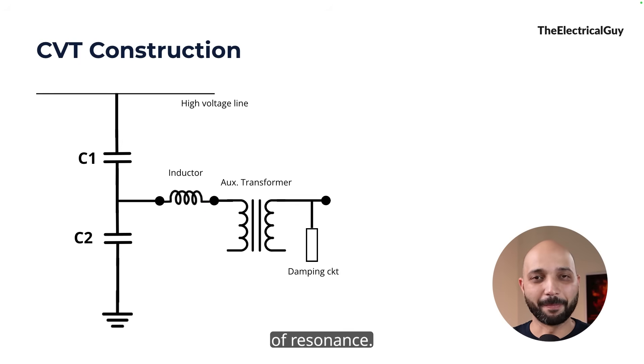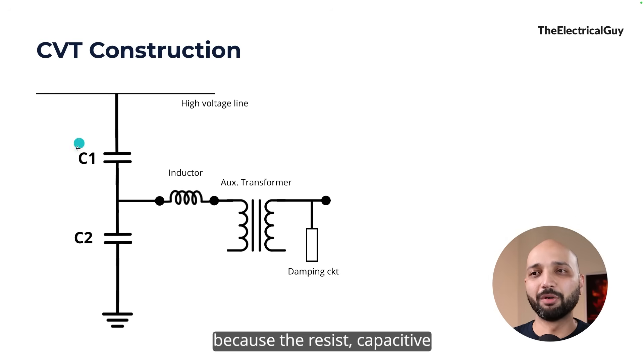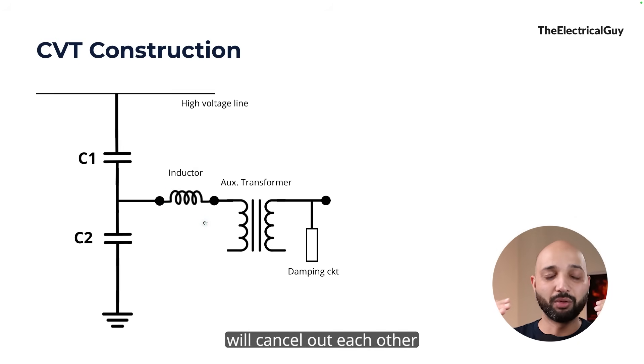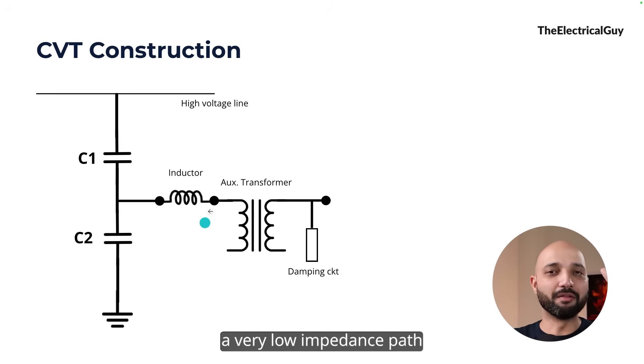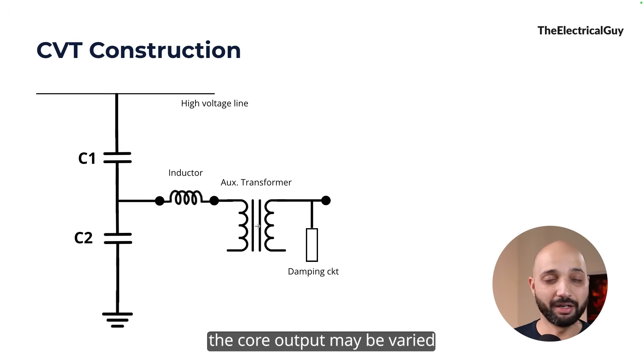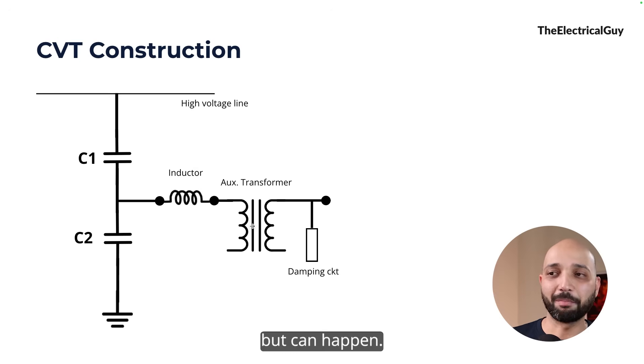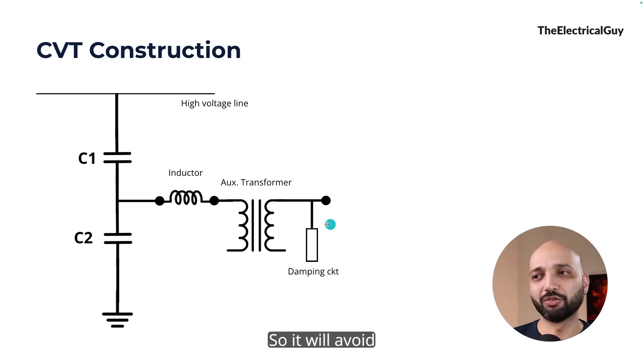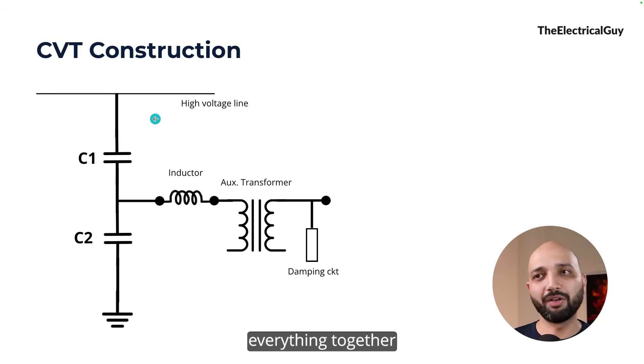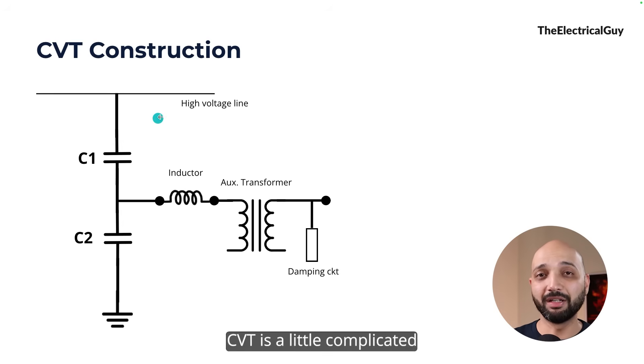Another issue is that since we have both a capacitor and an inductor in the circuit, there can be a situation of resonance — where the capacitive reactance and inductive reactance cancel each other out at a certain frequency, creating a very low impedance path. This can saturate the core and vary the output. It's a rare scenario, but to avoid it, a damping circuit is also included. Putting everything together gives us the capacitive voltage transformer, making its construction more complex than the IVT.